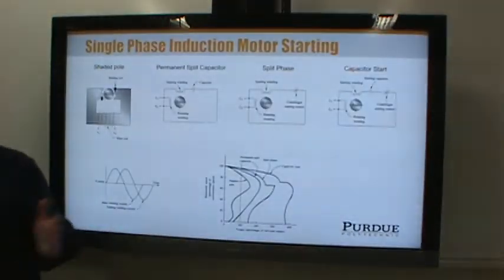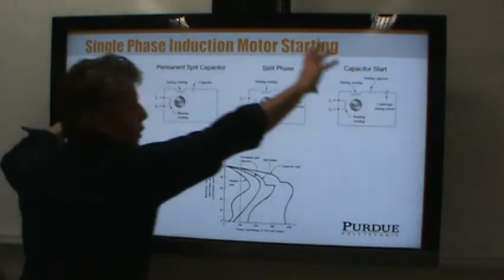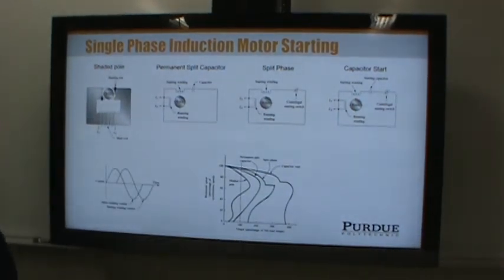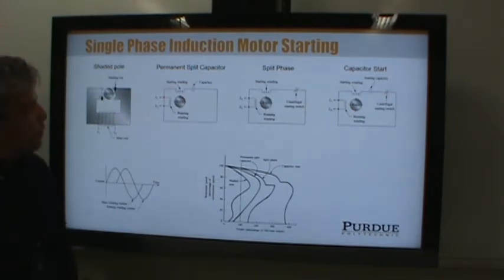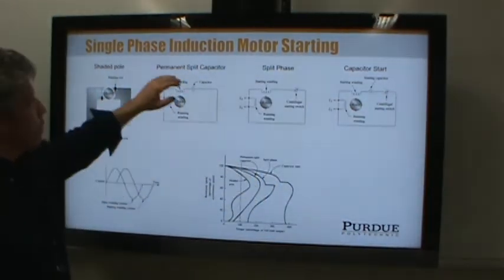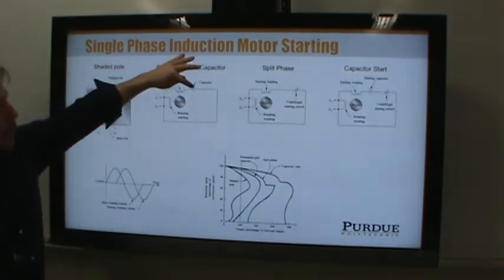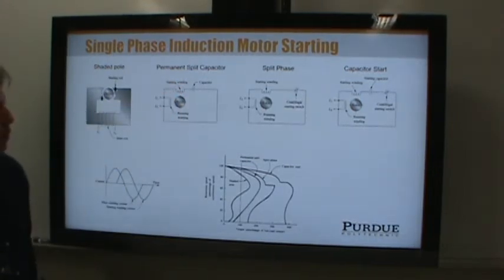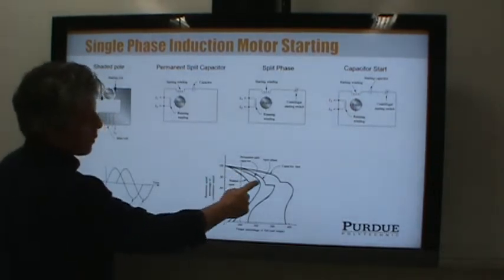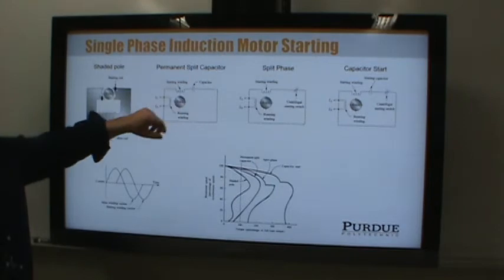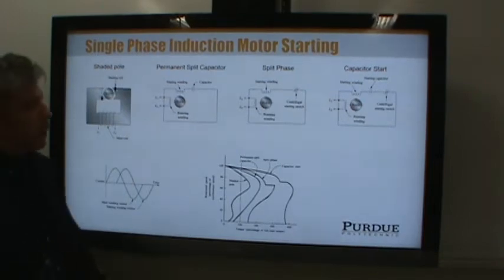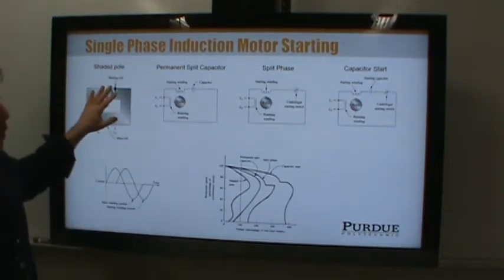So it's kind of like two ends of the spectrum — weakest, least efficient motor on one end; strongest, most efficient on the other, with these types in between. There's also the permanent split capacitor option: no centrifugal switch, so the start winding and capacitor always consume some power. You'd use that for smaller motors where the inefficiency isn't a major problem but where a shaded pole would be too inefficient to generate adequate torque.